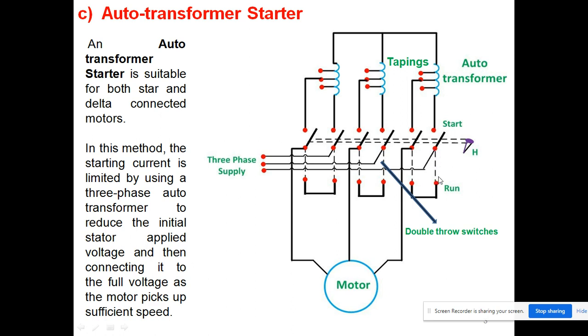This will connect here, this will connect here, or it will connect here. So what is happening here: the three phase supply is coming here and comes to here, and then goes back and comes to the motor. So now the supply is directly going to our motor, because now our motor picks up sufficient speed, around 80% of the rated value.